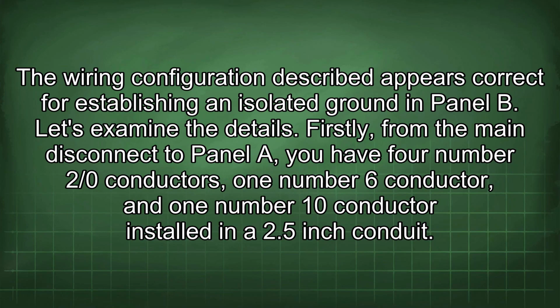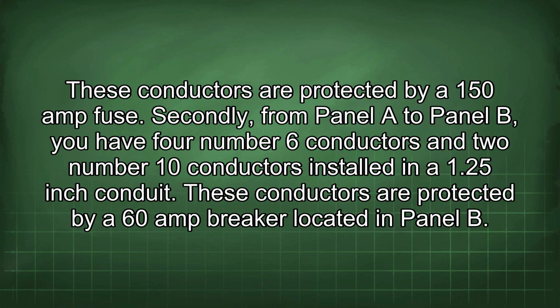The wiring configuration described appears correct for establishing an isolated ground in panel B. Let's examine the details. Firstly, from the main disconnect to panel A, you have 4 number 2/0 conductors, 1 number 6 conductor, and 1 number 10 conductor installed in a 2.5-inch conduit. These conductors are protected by a 150 amp fuse.